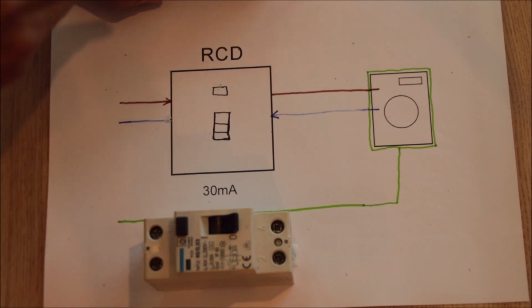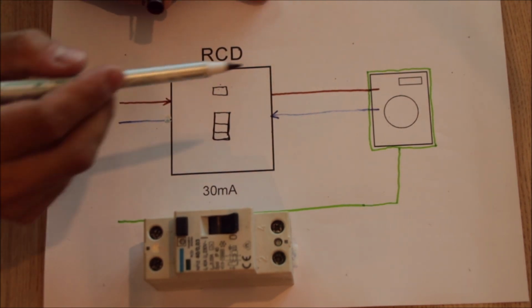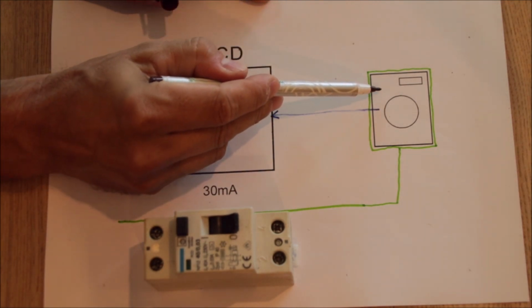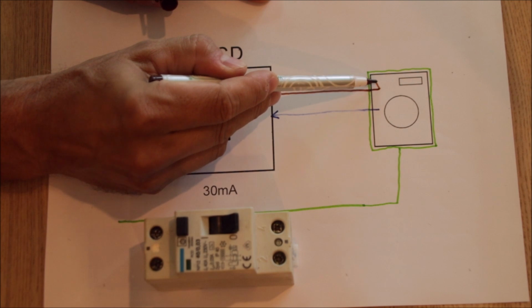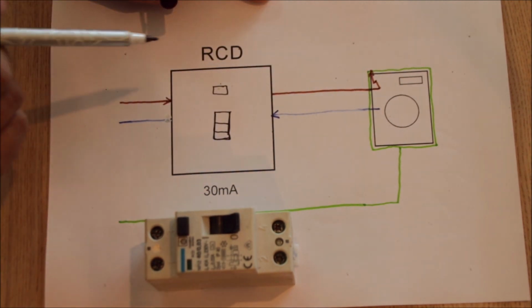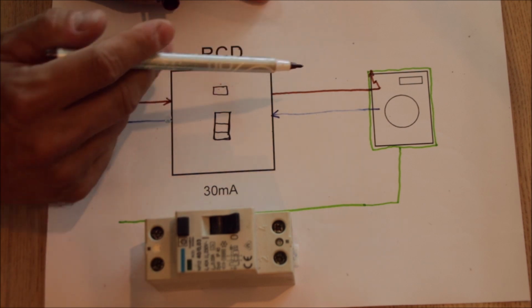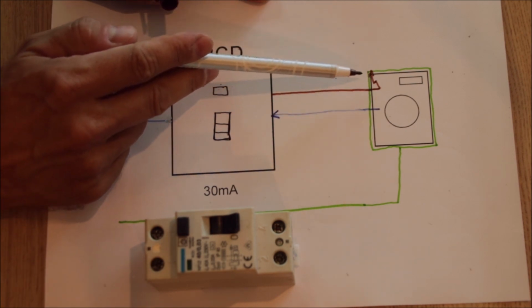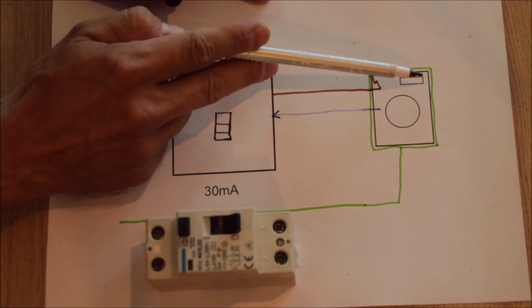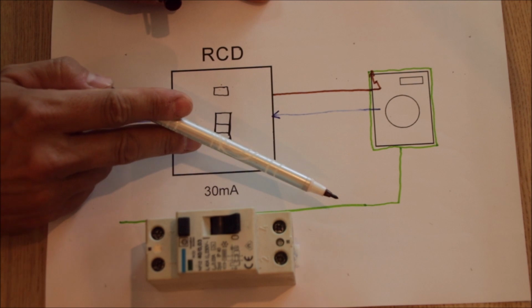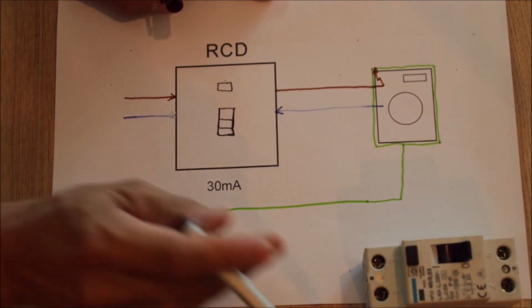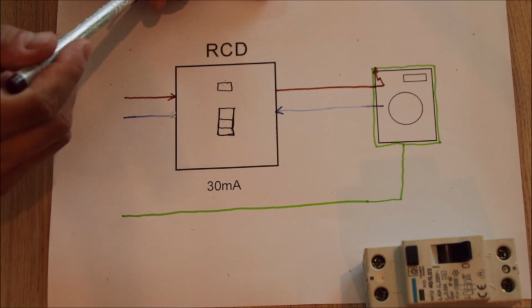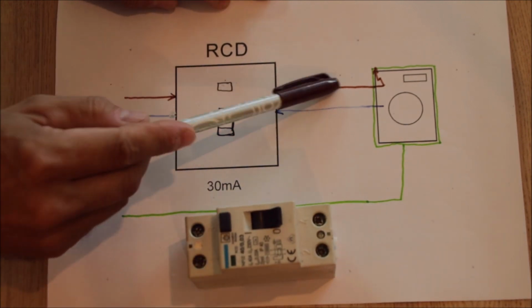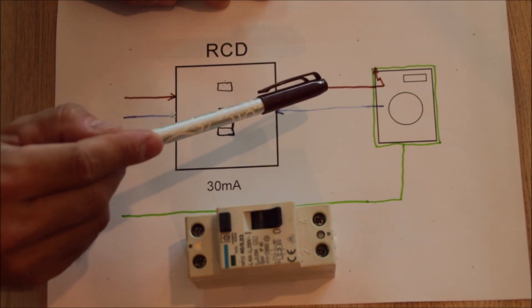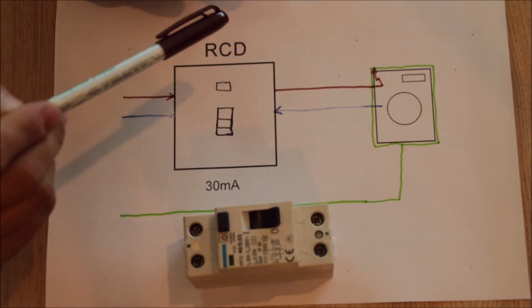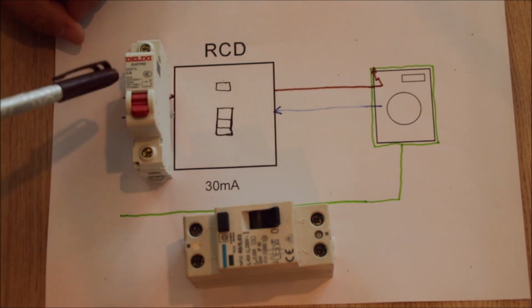Whenever there is some issue in a circuit, let's say we have either a dead short from L to the PE circuit, the current will flow over the protective shell, over the PE wire, and bypass our RCD. When it's a dead short, of course, this is a high current. This would not just trip the RCD, it will also, of course, trip a breaker.